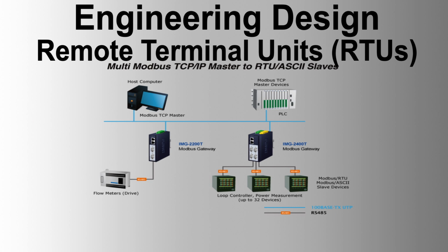RTU power supplies. The RTU power supplies are designed to provide all necessary power to support RTU operations with advanced power management functionality. Here are the key features and requirements. Power supply inputs. AC input: a wide-ranging input of 90 to 260 V, 50-60 Hz, from a UPS-based power source. DC input: a wide-ranging input of 20 to 60 V DC, nominally 24 V DC, from a solar power-based source. Power supply outputs. Load capacity: the total load capacity should be at least 50 watts.